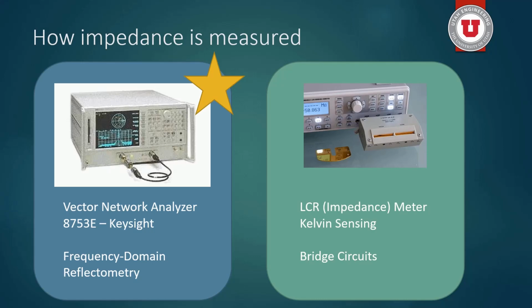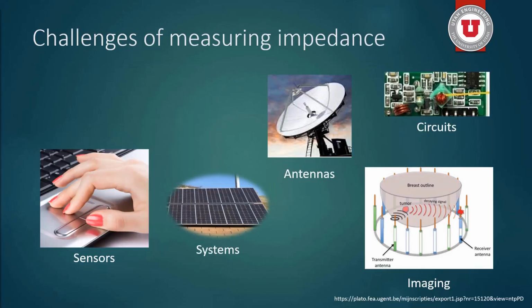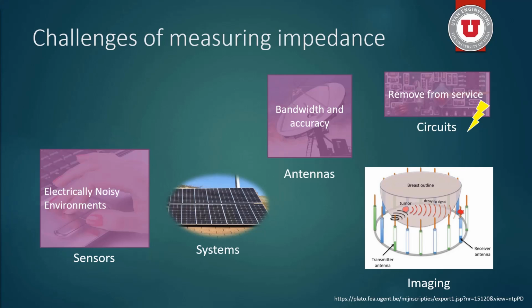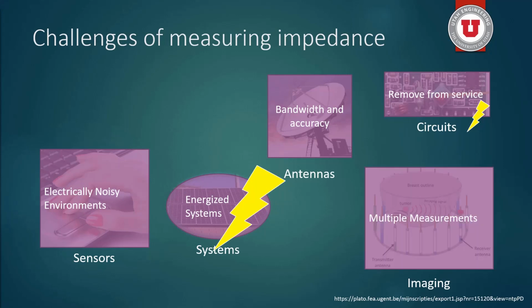Impedance measurements are conducted regularly. However, challenges arise when attempting to conduct measurements under certain circumstances, such as electrically noisy environments, needing to remove the device from service due to being energized in order to connect to the VNA or LCR meter, matching equipment capabilities to the specifications of the device under test, systems that cannot be de-energized, and conducting multiple measurements over a very short period of time.